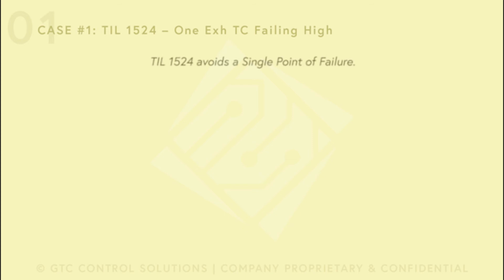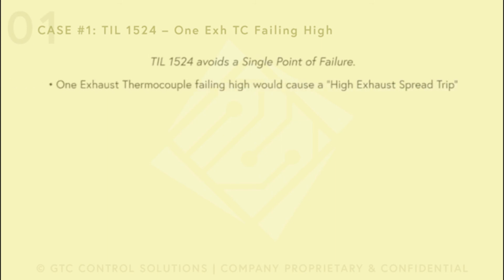So this TIL uses the second highest exhaust thermocouple to calculate the spread and avoids the situation. So the first thermocouple that fails high will not cause a high exhaust spread trip. But if you leave one failed high and you do not fix that, and a second thermocouple fails high, then yes, you will still have the high exhaust spread trip.